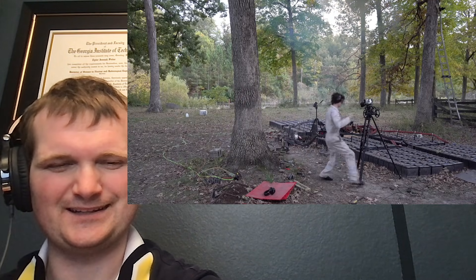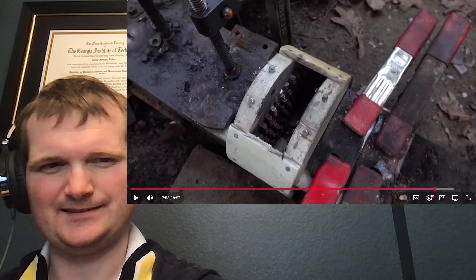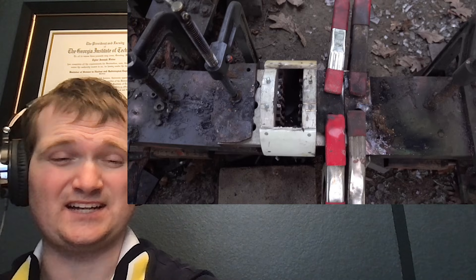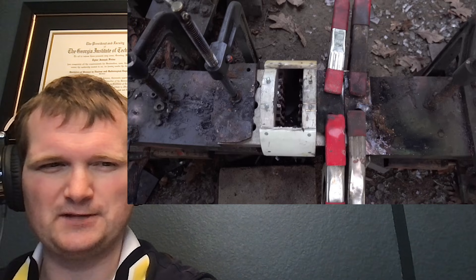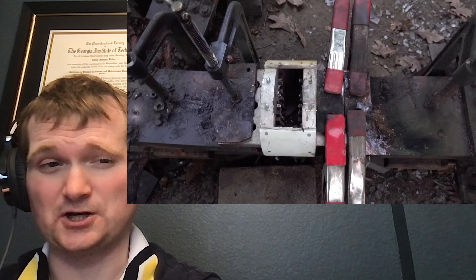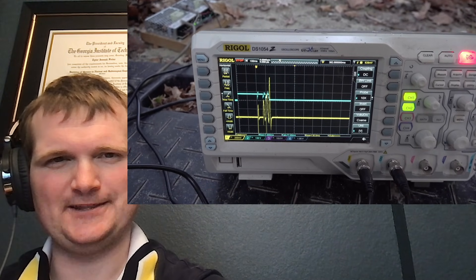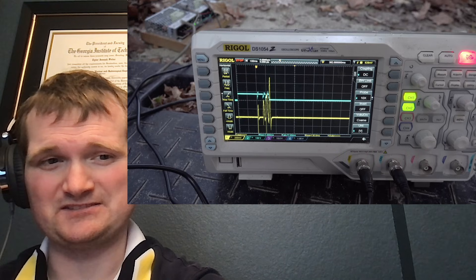It's at the center — I can see it smoke. I'm surprised how clean a burn-through that was; it completely vaporized those pieces. Kind of surprised given the low voltage being dealt with, but that definitely did it. Some of the higher energy systems with higher arc ratings — the typical arc flash labels that say 'no safe PPE exists' — are going to be on the low side of big transformers. The switch had a few hiccups, but once it finally closed, the fuse pulled 150,000 amps. That is well within the catastrophic end of main generator arcs in nuclear plants.